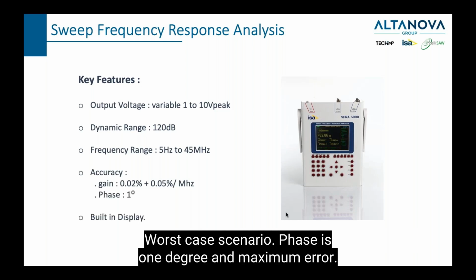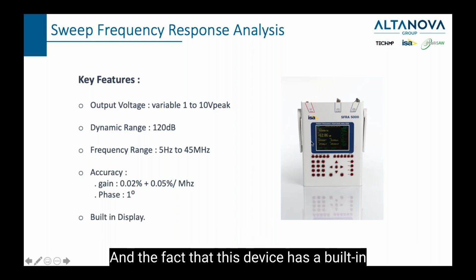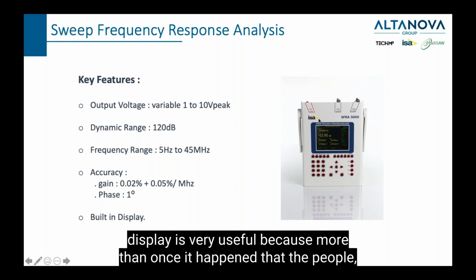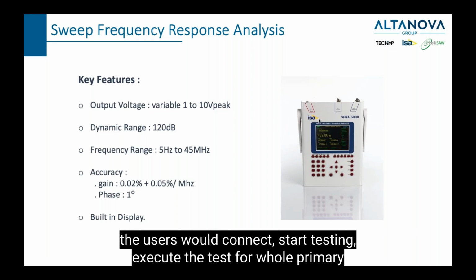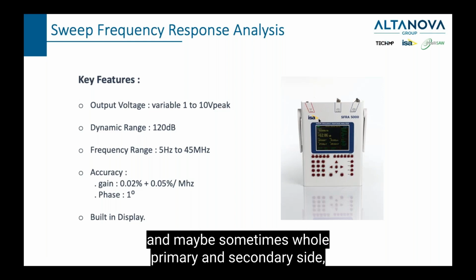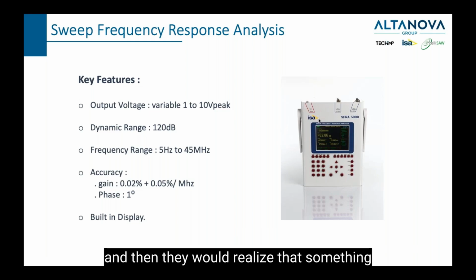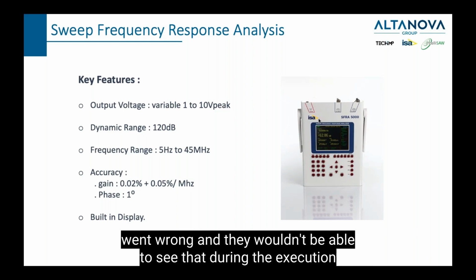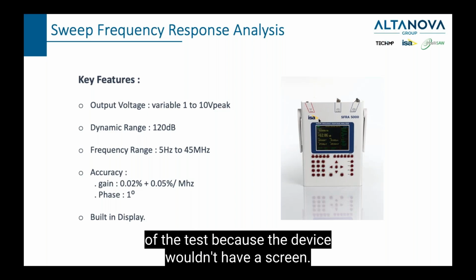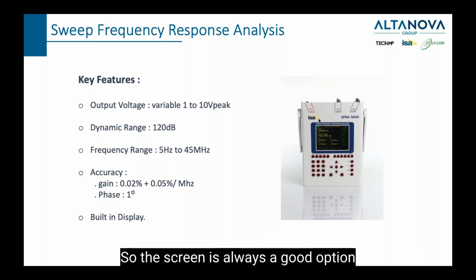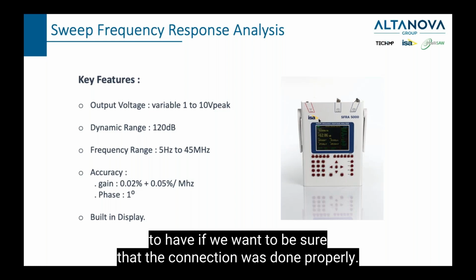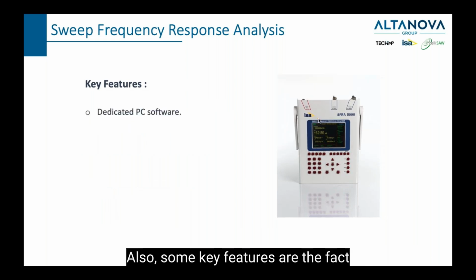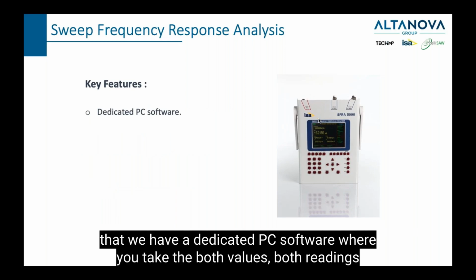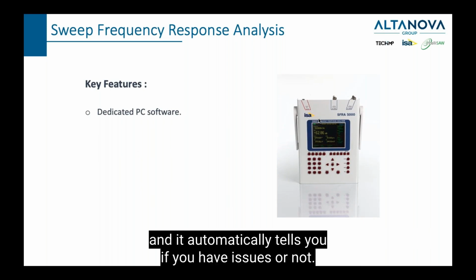Phase is 1 degree maximum error, and the fact that this device has a built-in display is very useful because more than once it happened that the users would connect, start testing, execute the test for the whole primary and maybe sometimes the whole primary and secondary side, and then they would realize that something went wrong. And they wouldn't be able to see that during the execution of the test because the device wouldn't have a screen. So the screen is always a good option to have if we want to be sure that the connection was done properly. Also, some key features are the fact that we have a dedicated PC software where you take both values, both readings, and it automatically tells you if you have issues or not.